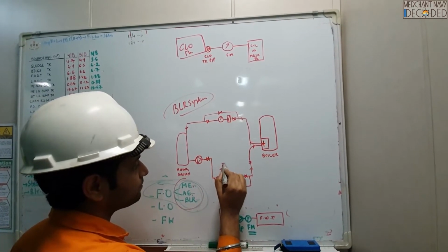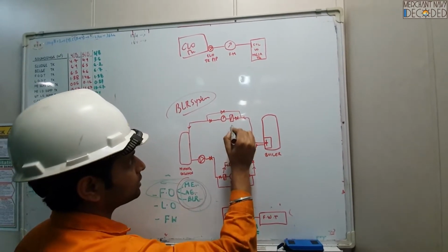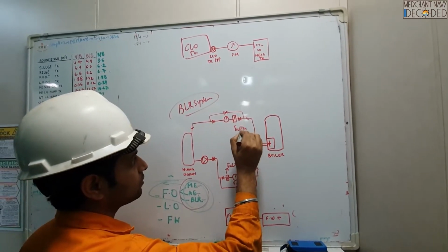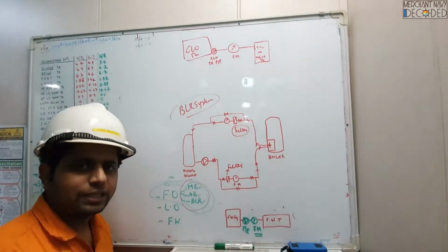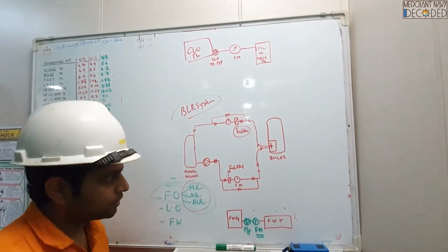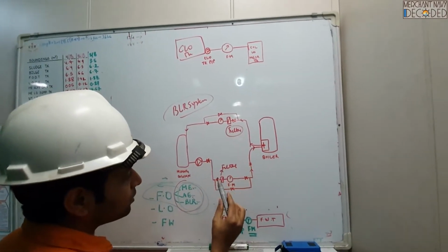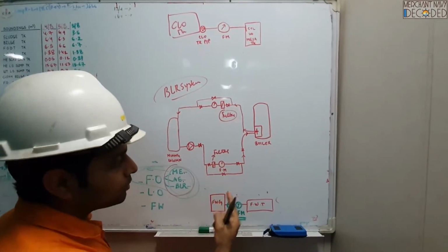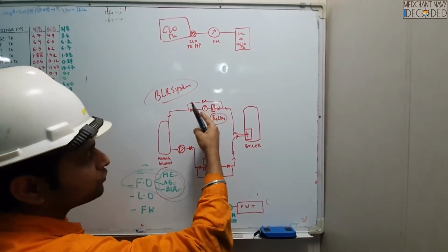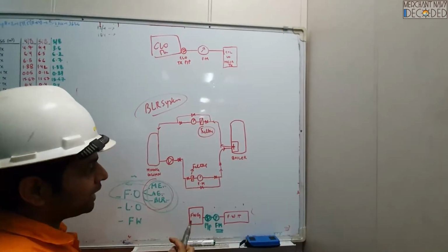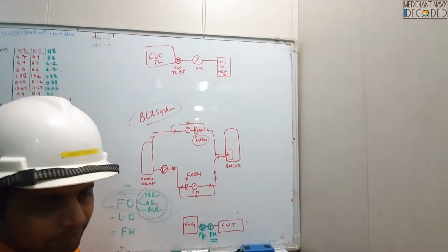This is a filter. These filters need to be cleaned every 3 months. Very, very important, because if these filters get choked, this flow meter is not going to turn much. So in that case, you will get false readings, not proper readings, right?